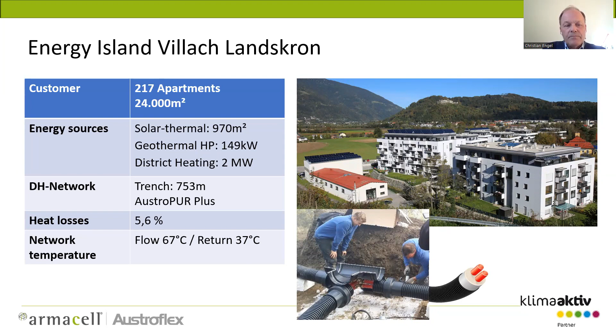What is important is that we run the system with very low temperatures, 67 degrees flow, 37 return, which gives a very low heat loss, important for the future. We want to reduce heat losses in the networks as one of our goals, and to increase renewables.